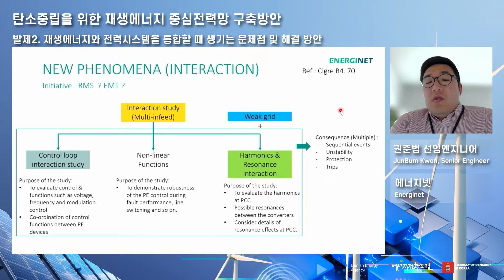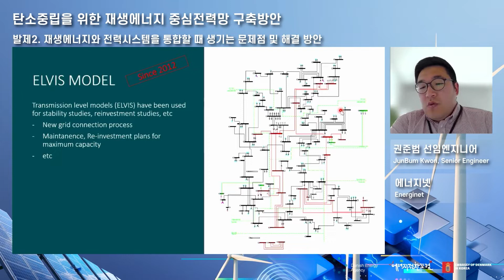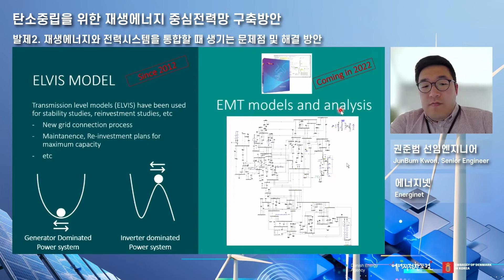As we expand renewable energy, cables and lines will be expanded and strengthened, and the impact on the lines needs to be accurately analyzed. The RMS model has a very large database accumulated over a long time, but for certain weak grid system analysis its accuracy was low. So currently we are using other EMT tools to develop system-level models, and the entire Jutland and Sjælland grid can be built on EMT for simulation. From planning to the entire analysis, we are going to do that based on the EMT system.